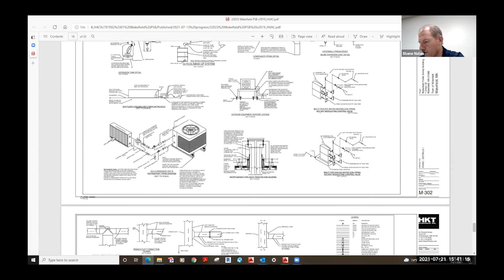On your schedule, Ben, those sizes, are you just going to check those? Because right now you're showing a 12,000 CFM rooftop unit, and then the chiller. I know in your report we carried, I think, a 120-ton chiller, but you've got 100 tons. Is 100 correct? Our load calcs have progressed, and I think we can do this with a 100-ton chiller, down from 120, which is good because that should be closer to the existing weight of the existing chiller.